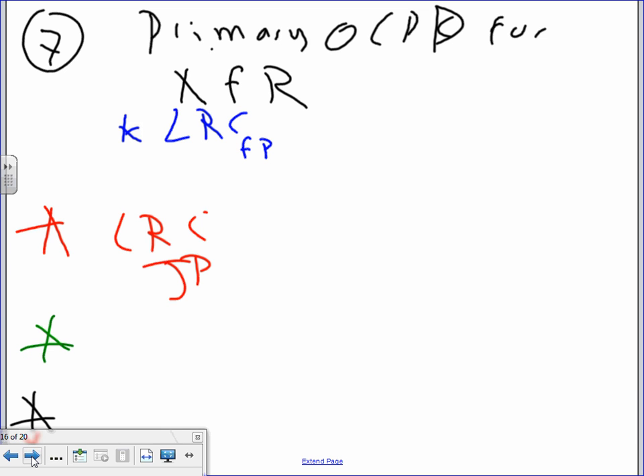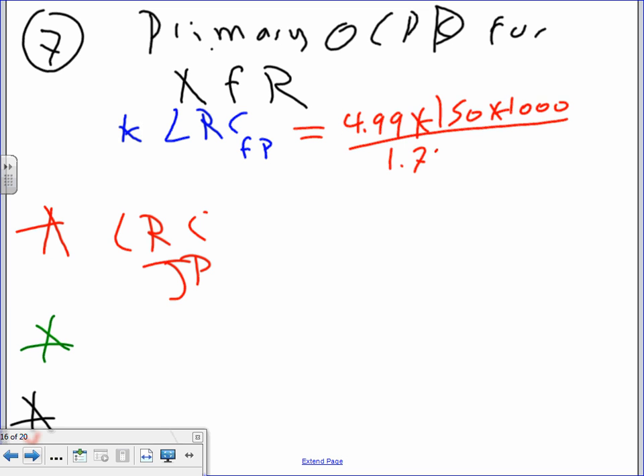So we're going to do the same thing, guys. Lock rotor current. Remember that lock rotor current business? For the fire pump, it's 4.99. That's the multiplier for it. 150 times 1,000. Divide everything by 1.73 times 208. And that'll get you a healthy 2,080 amps.